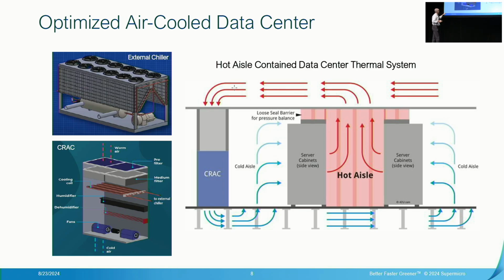Looking at the CRAC in this example: warm air comes in, chilled water goes into coils cooling that air, and then that air is pushed into the floor tiles up into the ambient side of the IT cabinets.